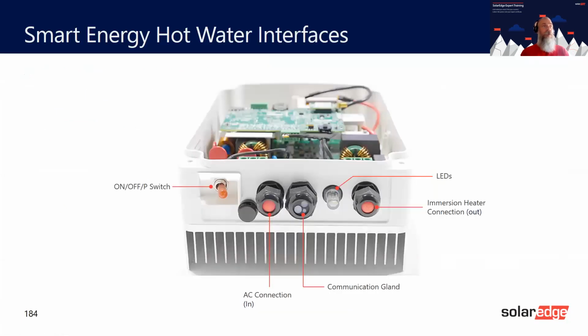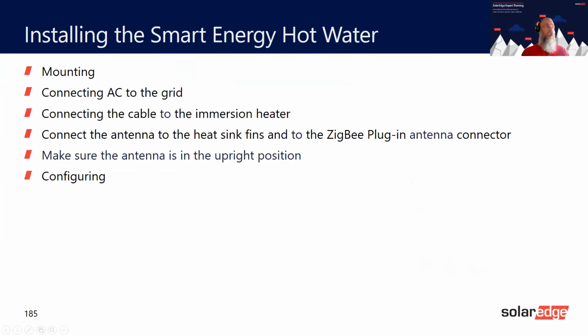So installing the smart hot water unit, just spend a bit of time on this because it's slightly different. You've got the immersion cable out and AC going in. So this is where the AC would come in. This is where it would go out. It's very important you do get the in and out correct. These are the communication cables in here, the LED indicator, and the on-off P switch as well. So basically, you mount it, connect it to the AC, connect it to the immersion cable. You then put the antenna in, then you set up the Zigbee communication, and configure.